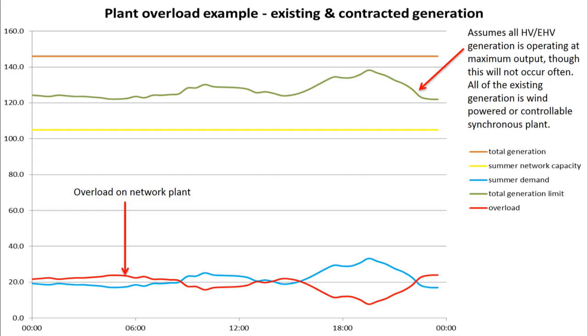But it's worth pointing out that this is the absolute worst case during summer, as it assumes that all the connected generation is running effectively flat out for 24 hours during that day, i.e. that's possible, but it's highly unlikely. At the moment, during the winter, with an intact network, there would be no overload on this network. So we've got some summer issues effectively on the Driffield network.